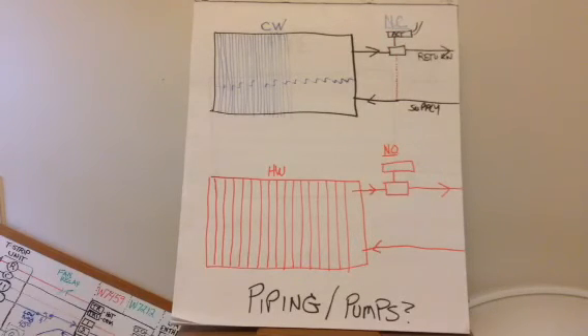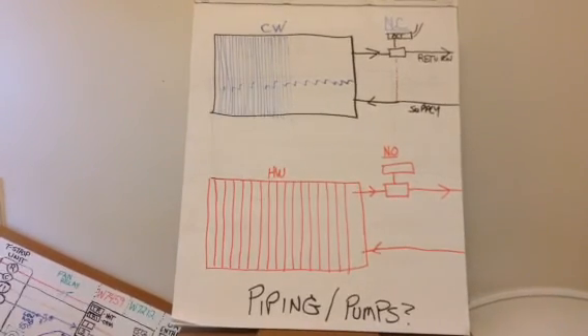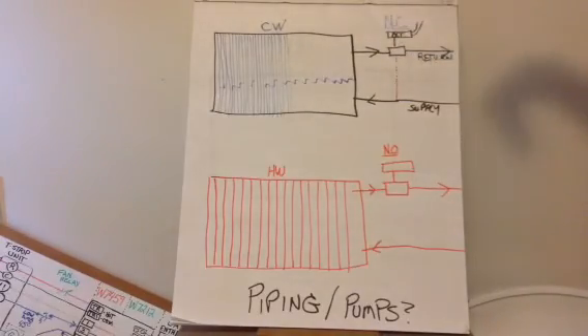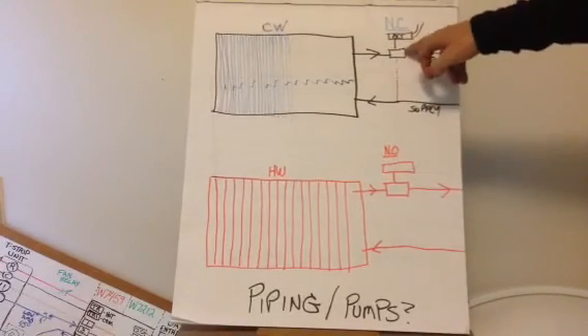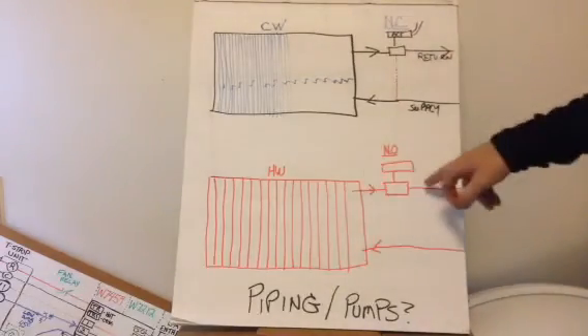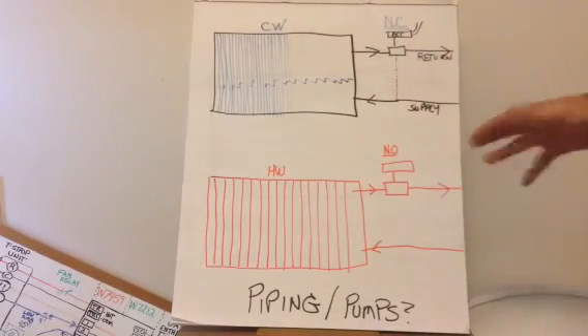So in a power failure or an alarm state, when you kill power to the unit, this hot water valve opens and allows hot water to flow through the coil. That quickly warms the coil, quickly warms the inside of the unit, and it's a part of the freeze protection. You don't want to have both of these coils the same, or both of these valves the same logic. You want this hot water valve to be a normally open valve. You want this valve to be a normally closed valve. Spring return. You kill the power to the unit, this valve shuts off the chilled water. This valve opens, allows hot water, if there is any, to go through the coil so it doesn't freeze.